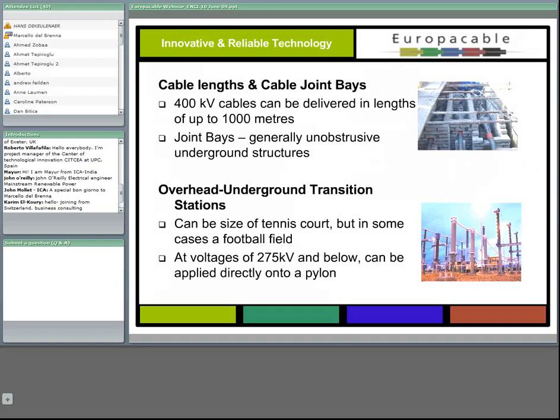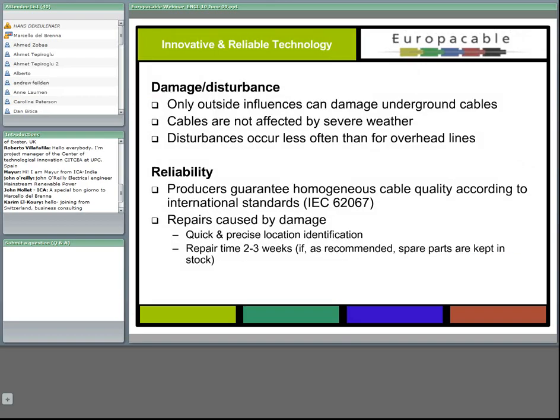As far as damages are concerned, experience accumulated at extra high voltage and high voltage levels shows that underground cables can basically only be damaged by outside influences. Being underground, they are not affected by weather, temperature, wind or gales, which means disturbances occur less often than for overhead lines.